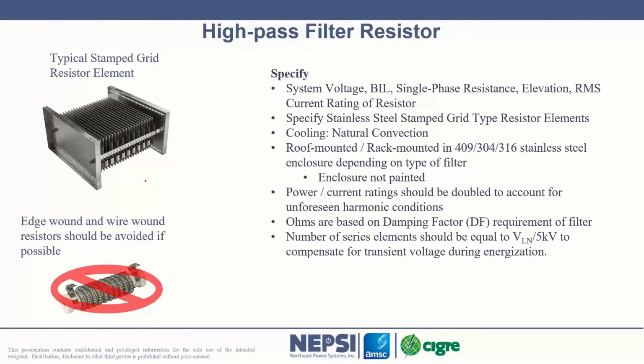The stamp grid design is shown here. If you go with a higher watt rating than you need, one of the other advantages is that I can tap off of these points here and come up with lower values of R, or if you ship it at some lower value here, we can then increase the resistance. So it's what we would call designing flexibility into a harmonic filter. It allows you to tap the resistor if you can put more rating into the resistor. So putting more rating in the resistor gives you a backup plan.